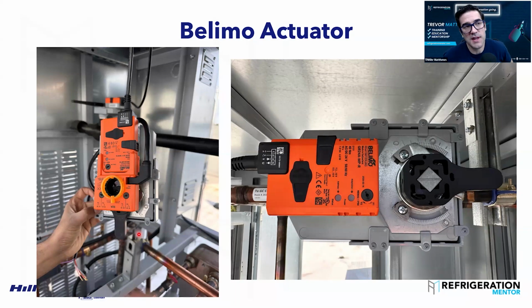Belimo's, on your standard rack, you might have just had a 3-way solenoid valve, where you see more and more on CO2 racks is a three-way actuator with a Belimo actuator on it. I do have a quick question for you. I had someone call me up last week, maybe, asking about the stops here. So if you put this stop right here at 50%, that means it won't close or open over that percentage. Is that correct with these stops here?